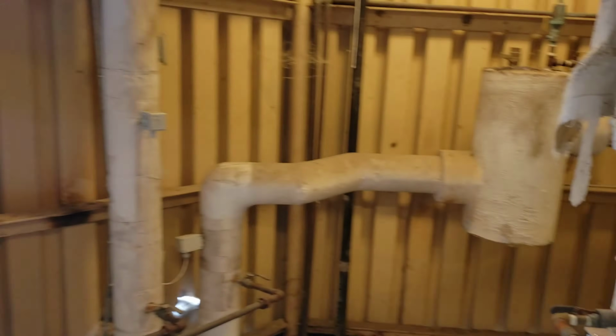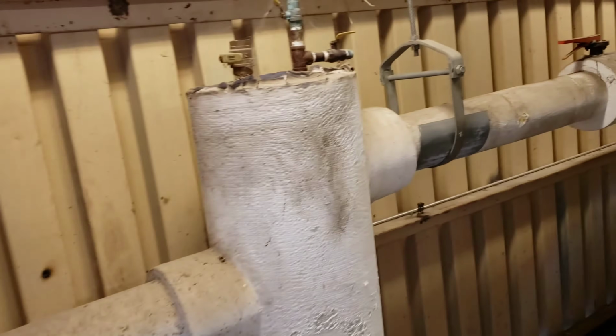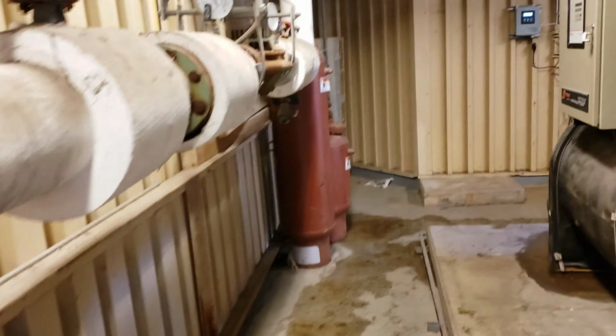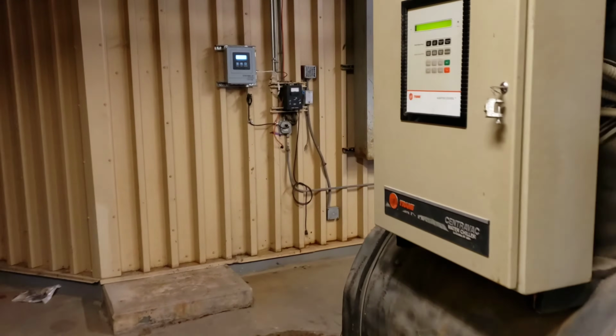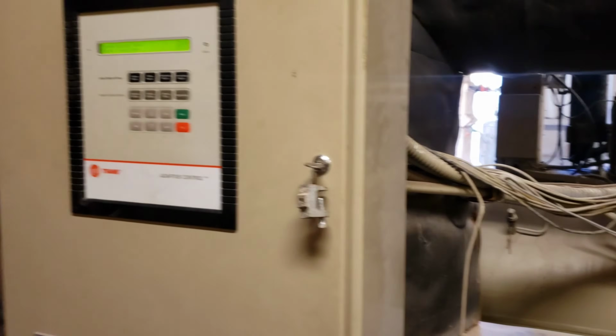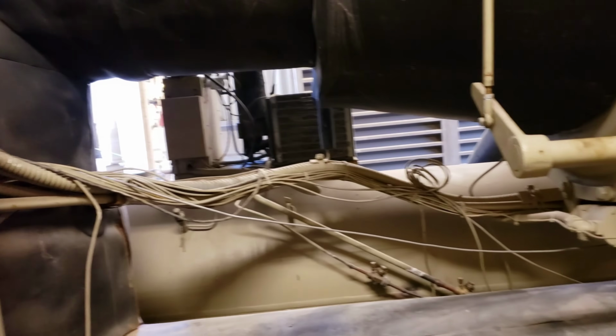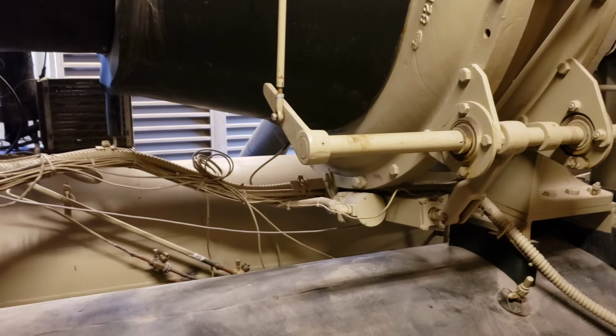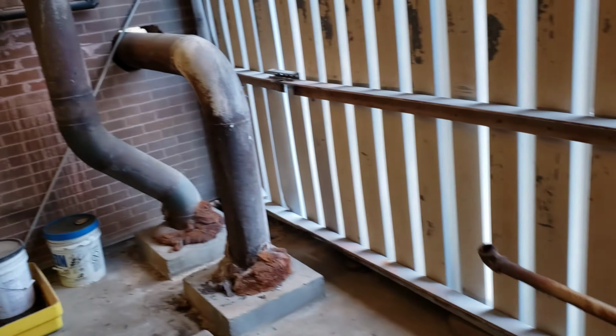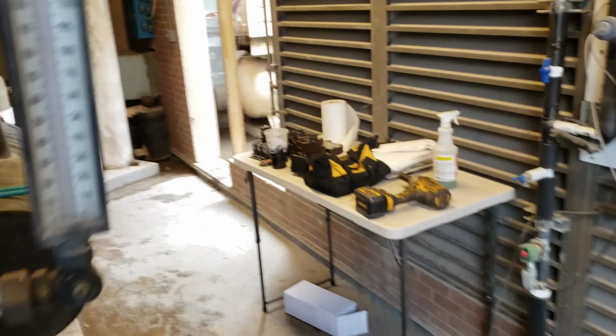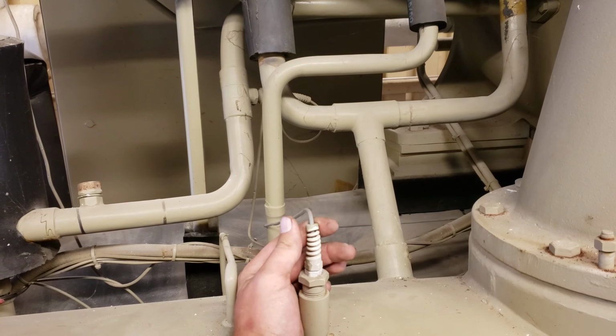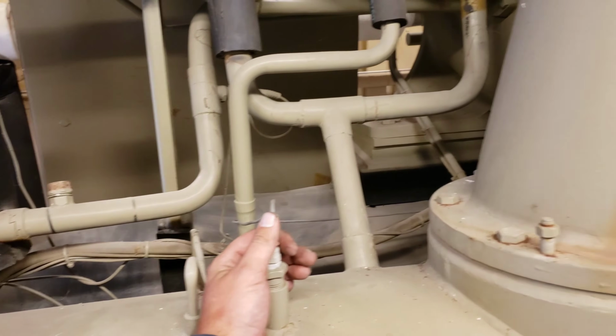That fixed that. Got it turned on. It was having a major surging issue. I was looking at the approach and looking at the condenser temps, and it was looking fine. I didn't see any explanation, any reason, nothing as to why it would be surging. And so I finally hooked my Testo gauges up and started checking it, and realized that my discharge temperature sensor, which is reading discharge saturation, which is how this machine determines condenser pressure, had failed. It was reading about 10 to 15 degrees off. And so that did a couple of things.